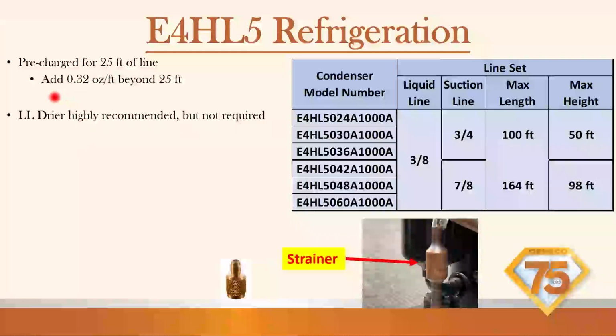Pre-charge is for 25 foot of line. If you have a 50-foot line, you're going to go 25 times 0.32 ounce per foot. Beyond 25 foot, that's your adder. There are no pressure curves in these outdoor units to do charging. We've asked for them. They are going to act like our standard systems for charging in heating mode. But again, go off of the 0.32 ounce per foot beyond the 25 foot, and you should be good to go. And verify your second stage compressor is coming on after the 20 minutes by amperage. You should watch your pressures go up too if you're at 100% compressor speed.